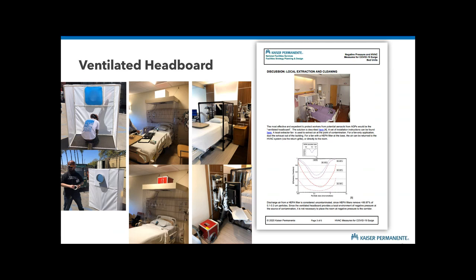HEPA filters actually get more efficient as the particle size goes down. I don't know if you can see that, but as you get towards those 0.01 or 0.02 micron particles, their efficiency actually rises, and there are some weird reasons for that, Brownian motion and things like that. But that is important to recognize. Again, I love the history of the HEPA filters. They're supposed to remove alpha and beta nuclear particles so that you don't turn into a ghoul, but they are effective on small particles. I think we need to trust our HEPA filters, or better yet, don't trust them, test them.